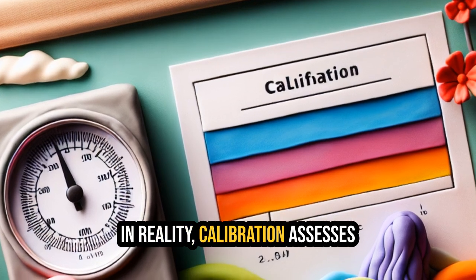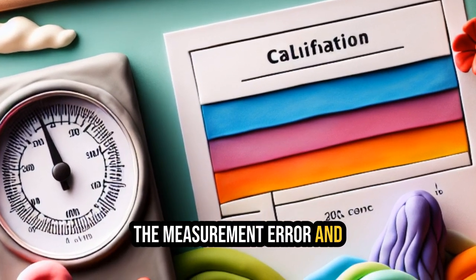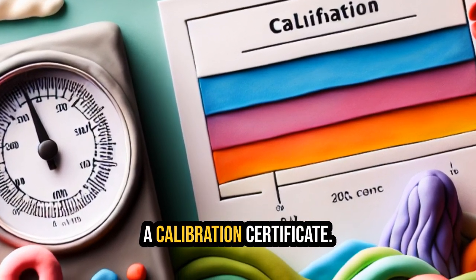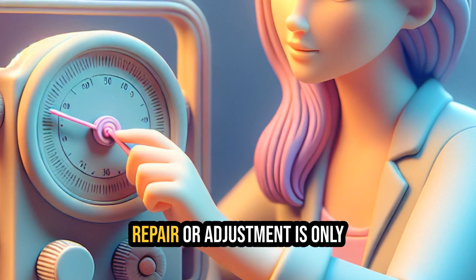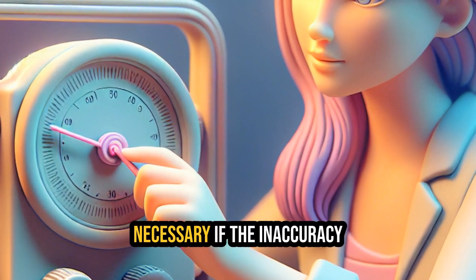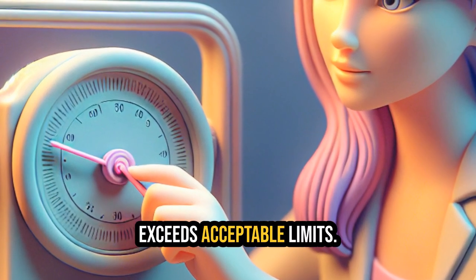In reality, calibration assesses the measurement error and certifies accuracy through a calibration certificate. Repair or adjustment is only necessary if the inaccuracy exceeds acceptable limits.